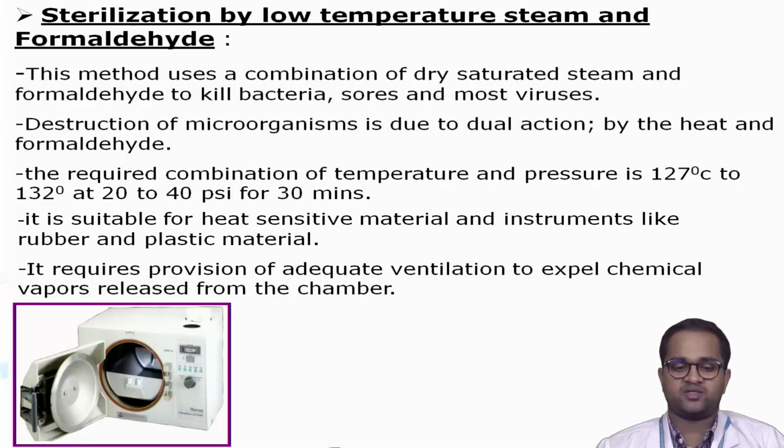Sterilization by low temperature steam and formaldehyde. This method uses a combination of dry saturated steam and formaldehyde to kill bacteria, spores and most viruses. Destruction of microbes is due to dual action, that is by heat and by the formaldehyde chemical property.